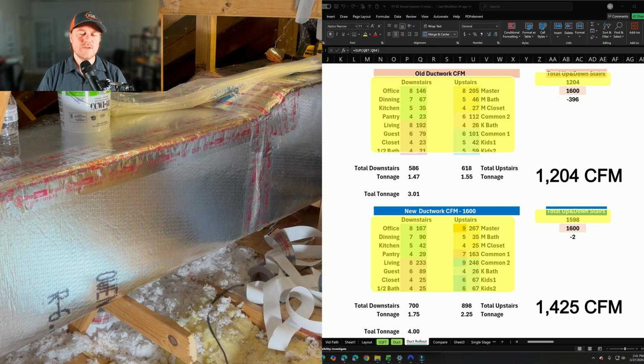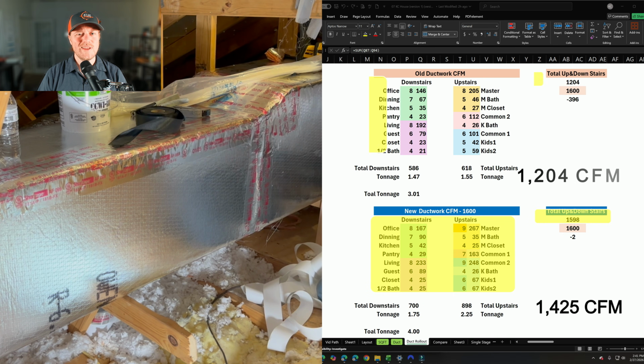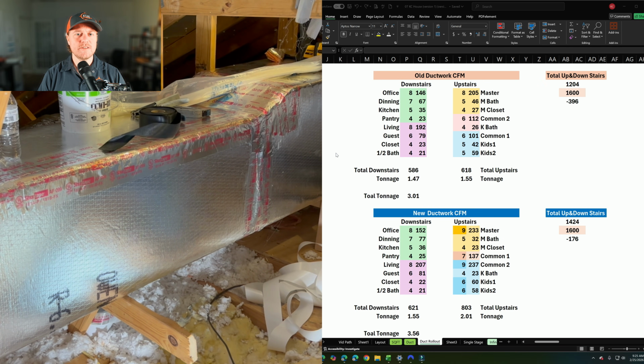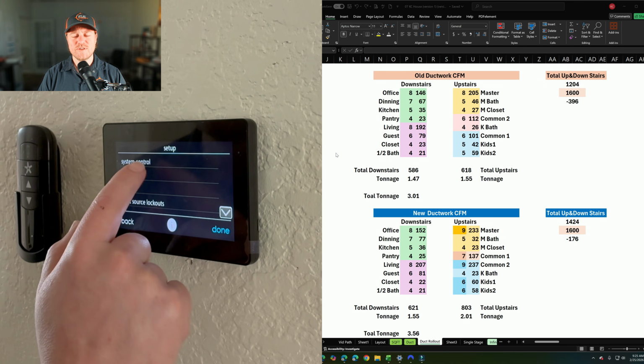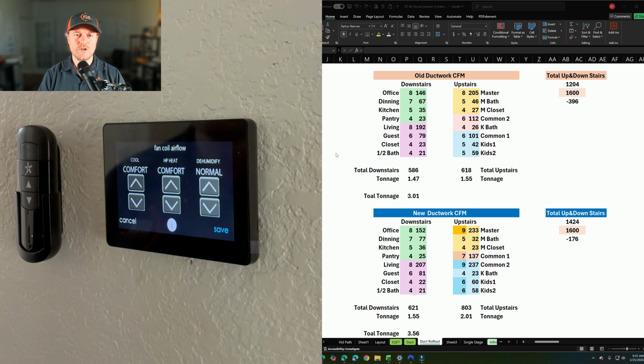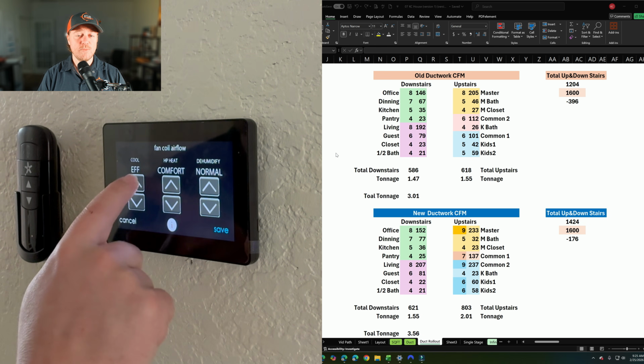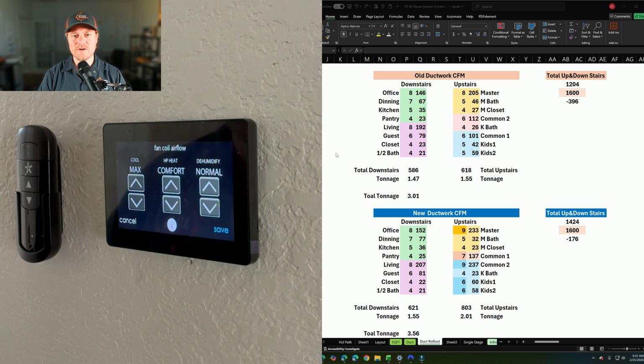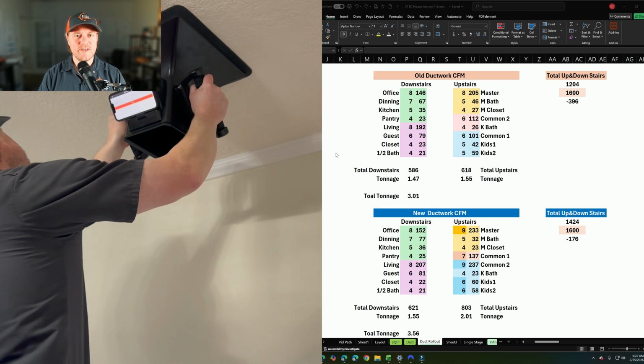Now let's max out the system at 1600 CFM and see what that does. First things first, I need to make some adjustments to the thermostat, change some settings to max airflow, and that should push 1600 CFM, similar to the single stage Amana that we're comparing to. Now time to redo our CFM test.